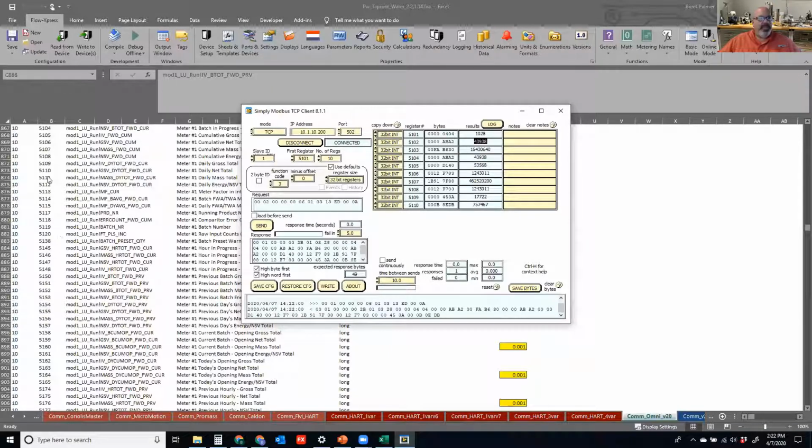I have to know on this side what I just polled for, and I have to put it somewhere over on this side. With the database, with just web service commands, I'm able to get the information out of the Flow computer, and I'm able to do it more efficiently. I'm not always polling for all of these registers to see when something changes. I'm polling for a status bit, and I'm looking at a checksum value. When that checksum value changes, I know to ask for a different request to get all my information back.